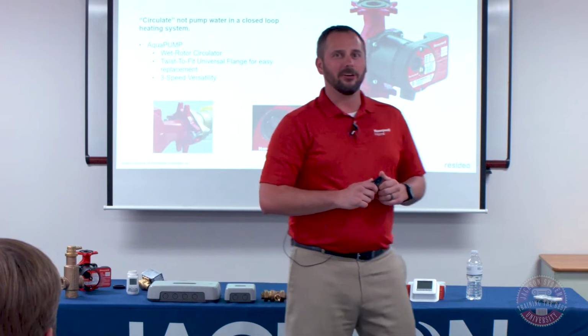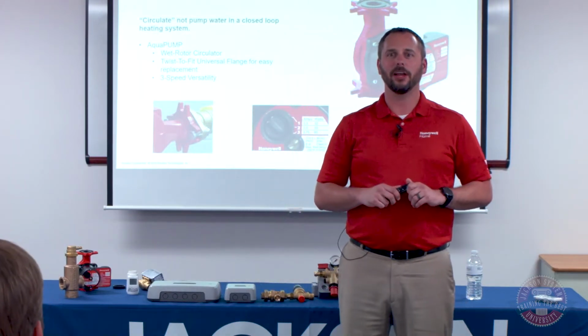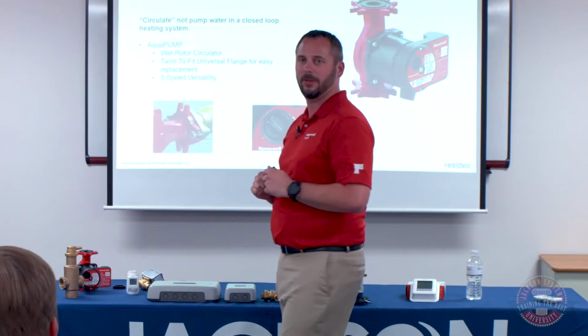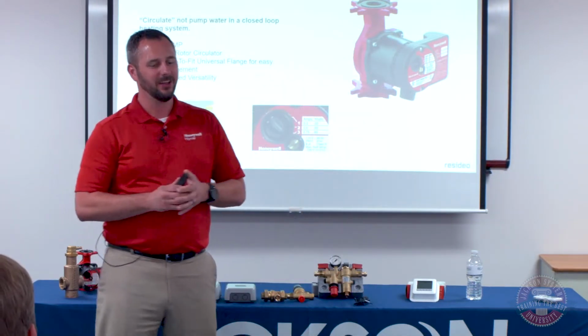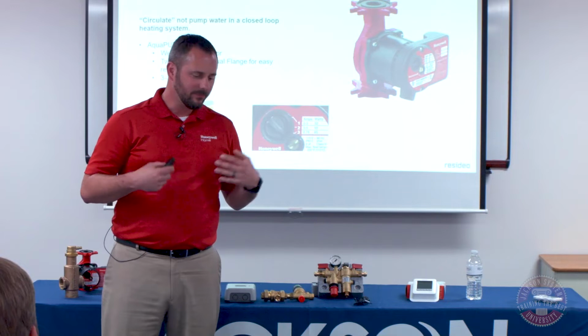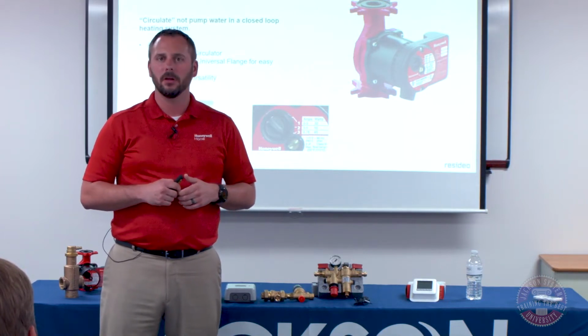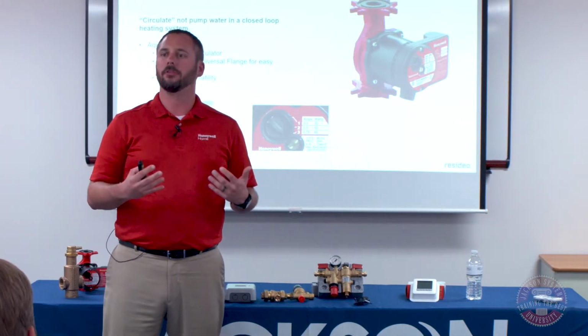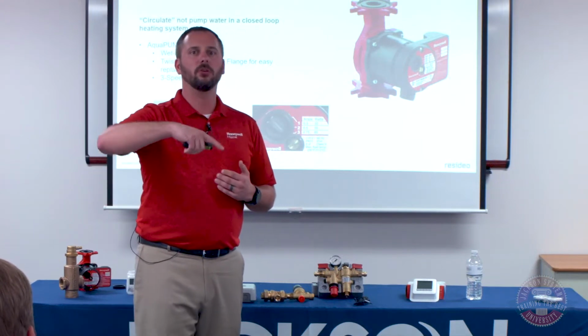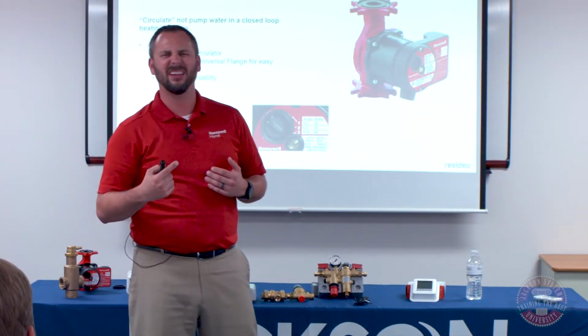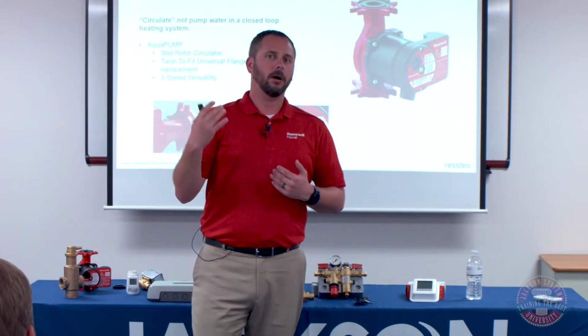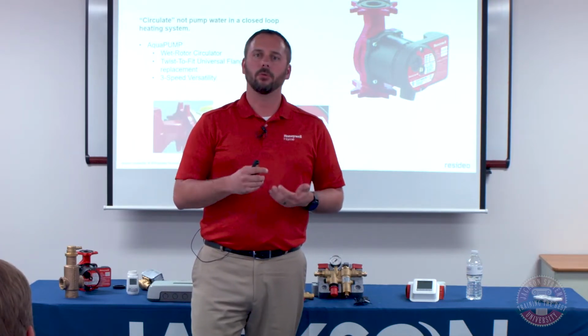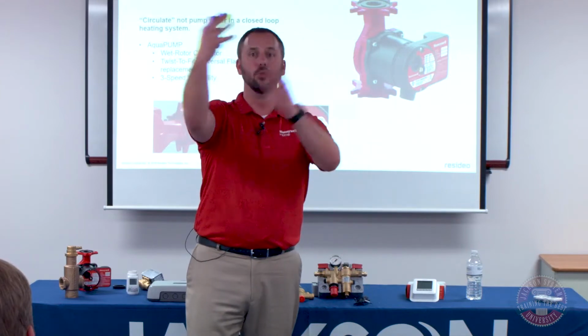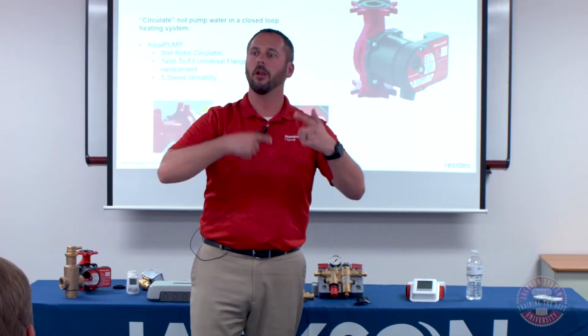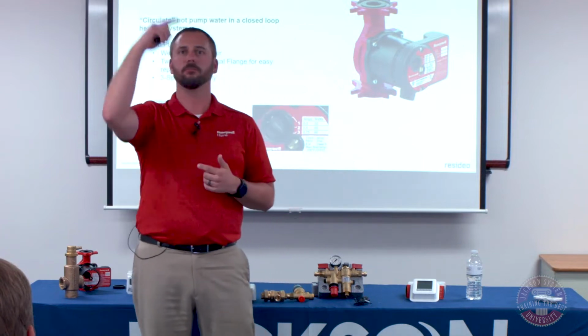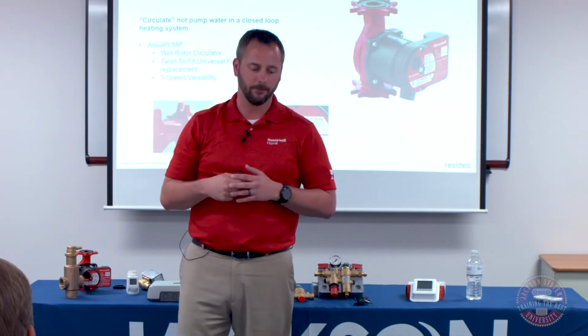So talking about circulators, I put the word circulators up there instead of pumps. And I did that intentionally. When you're looking at a hydronic heating system, it's not technically a pump because it's a closed loop system. Every bit of pressure that you put into it is going to come back on the opposite end. So it's kind of like a Ferris wheel effect. Pumps are used like sewage ejectors and sump pumps, where you're taking a body of water and you're moving it physically from one location to another. In our world, we're circulating the water. We're literally just putting it up here and then it's coming back to us on the other end.